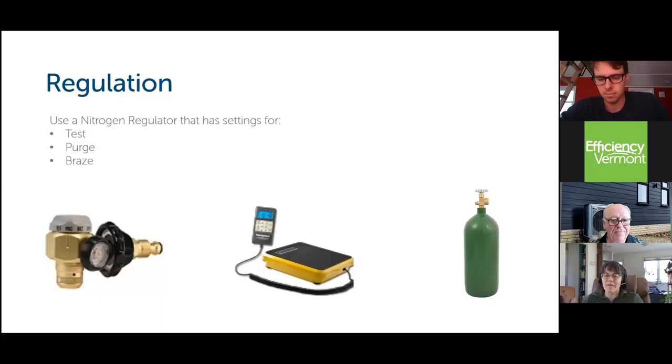And then there's a follow-on question about using the same pressure for multi-split systems, by which I think we're talking about multi-zone systems with several refrigerant lines. Yes, when you get into something like VRF and you get into something that is multiple systems and large systems, then I would go with the manufacturer's recommendations. You're not going to be doing a test and watching it for 10 or 15 minutes. Some of those install manuals are recommending overnight testing, maybe even longer, and that's 600 PSIG. And for that, I would definitely go with the manufacturer's recommendations. I'm only talking about a simple install, when you're just trying to get the low side test done with the line set.